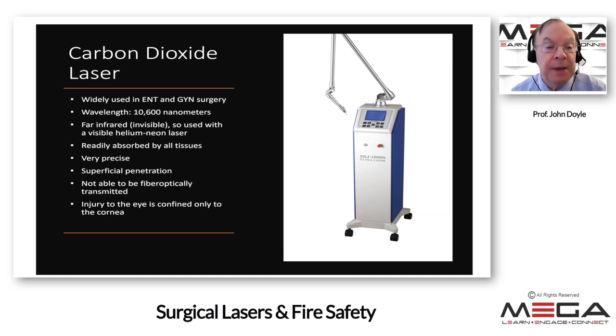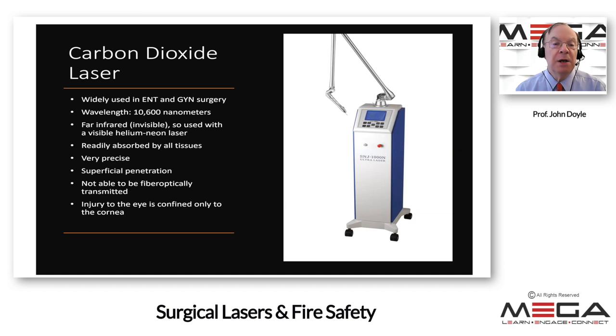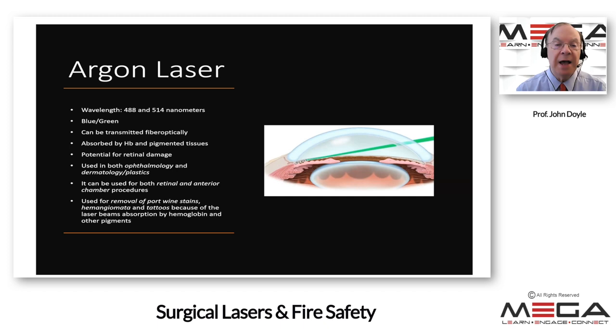The carbon dioxide laser has one of the largest wavelengths — over 10,000 nanometers. Because of its large wavelength, it is invisible, so it's used with a visible helium-neon targeting laser. It is widely used in ENT and gynecological surgery, very precise but only superficially penetrating. It cannot be transmitted fiberoptically, so special arrangements are needed. If eye injury occurs, it is confined only to the cornea.